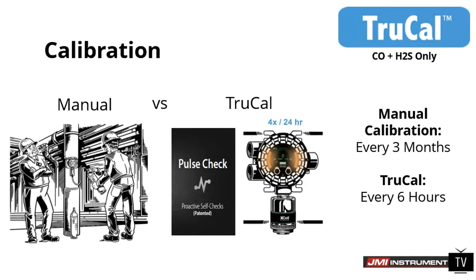Now we have manual calibration versus TruCal. When we talk about TruCal, if you note in the top right corner of your screen, the TruCal function happens only for carbon monoxide and hydrogen sulfide sensors. Going back down to the meat of the slide, part of what the TruCal function does is what we call a pulse check. That pulse check happens 4 times a day, every 6 hours, over a 24-hour period, and repeats itself.